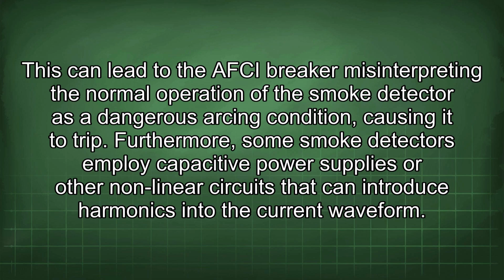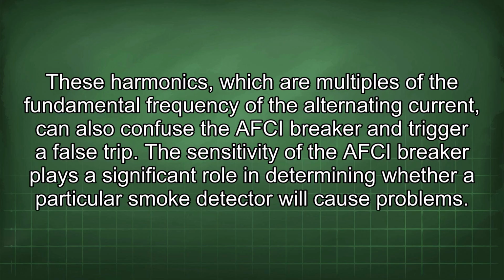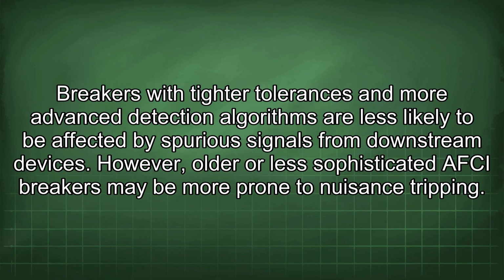This can lead to the AFCI breaker misinterpreting the normal operation of the smoke detector as a dangerous arcing condition, causing it to trip. Furthermore, some smoke detectors employ capacitive power supplies or other nonlinear circuits that can introduce harmonics into the current waveform. These harmonics, which are multiples of the fundamental frequency of the alternating current, can also confuse the AFCI breaker and trigger a false trip. The sensitivity of the AFCI breaker plays a significant role in determining whether a particular smoke detector will cause problems. Breakers with tighter tolerances and more advanced detection algorithms are less likely to be affected by spurious signals from downstream devices. However, older or less sophisticated AFCI breakers may be more prone to nuisance tripping.